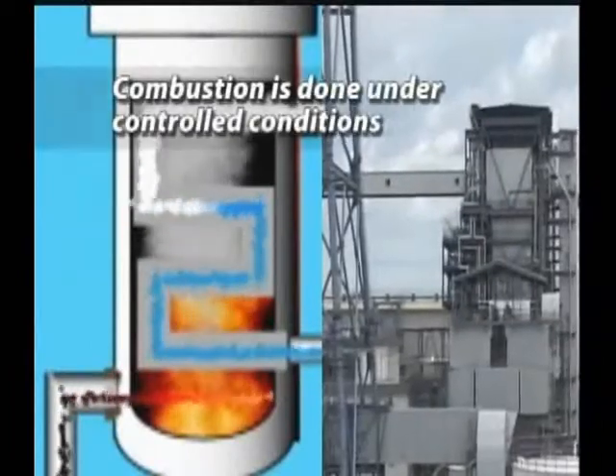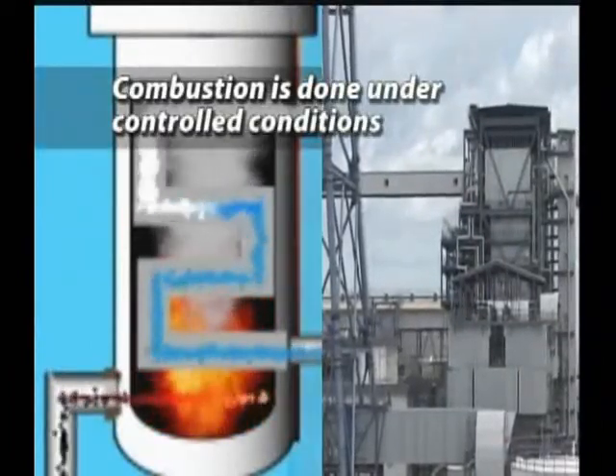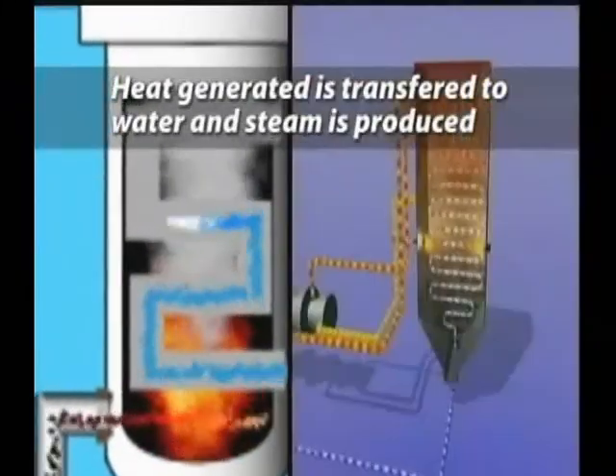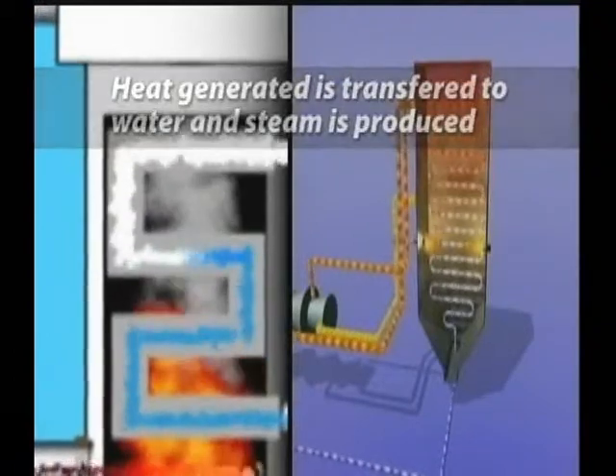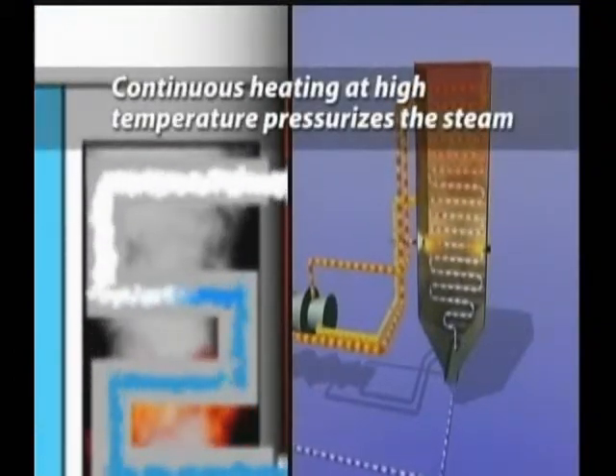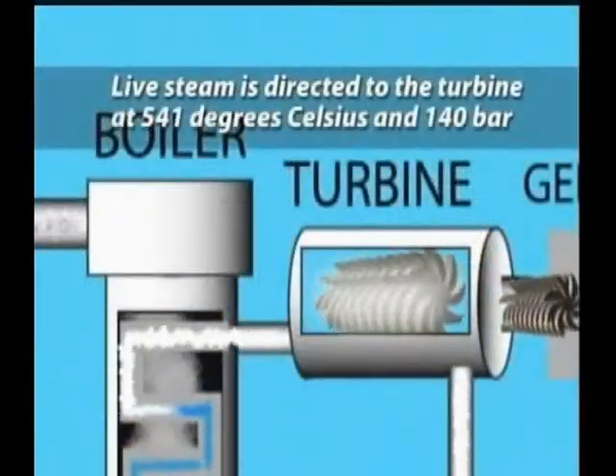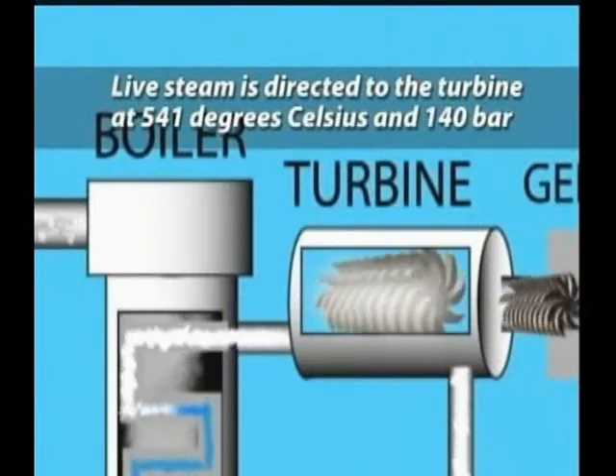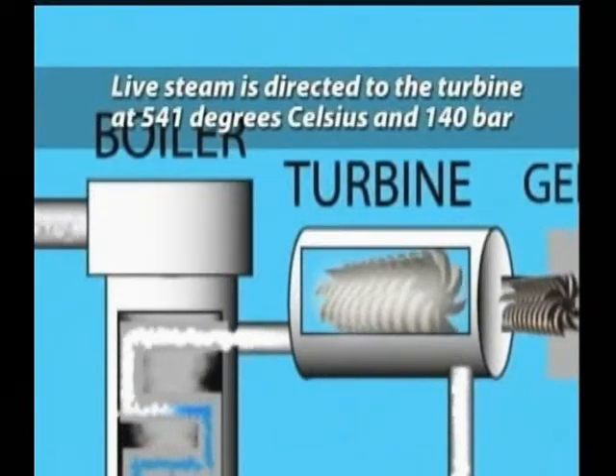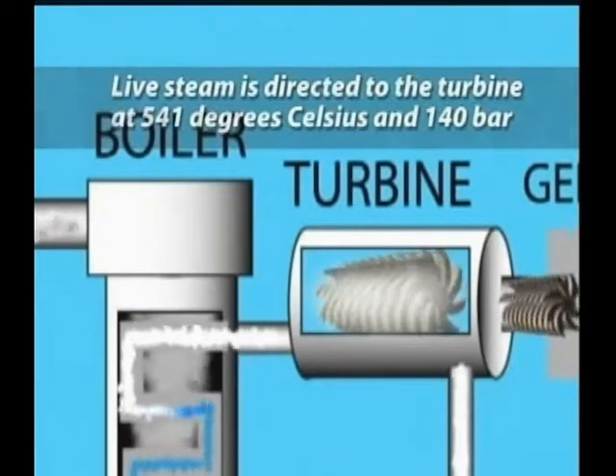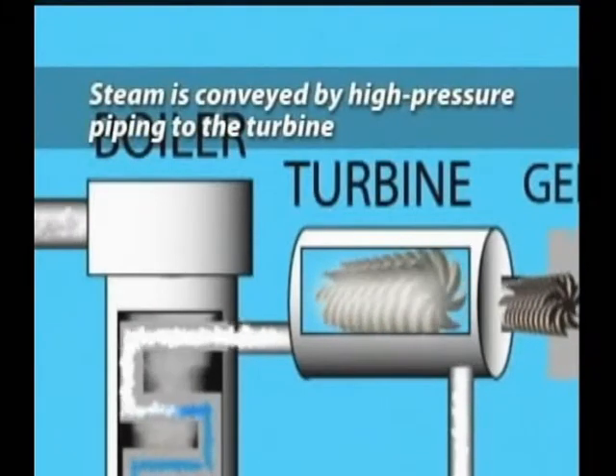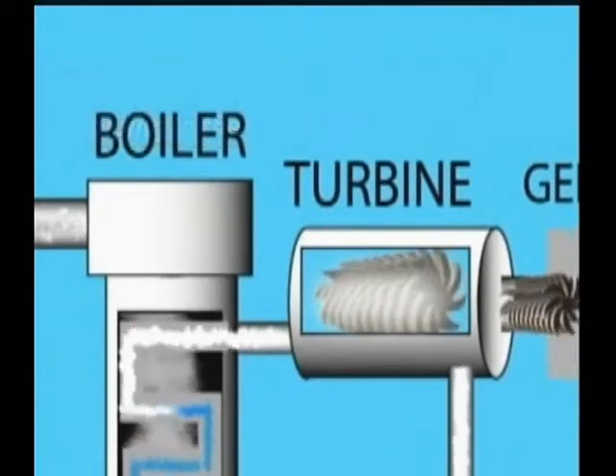Coal entering the boiler furnace is combusted under controlled conditions to minimize emissions. The heat generated is transferred via the boiler heating surfaces to water, thus generating steam. With continuous heating at high temperature, the steam is pressurized. The resulting live steam is directed to the steam turbine at a temperature of about 541 degrees Celsius and a pressure of 140 bar. Live steam from the boiler is conveyed by high-pressure steam piping to the steam turbine.